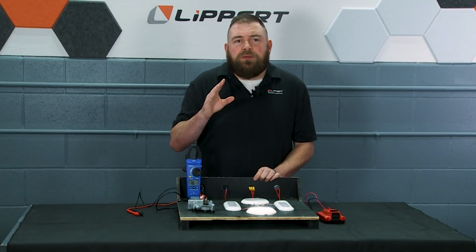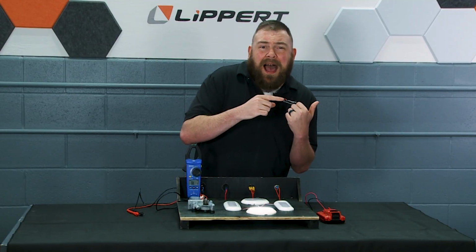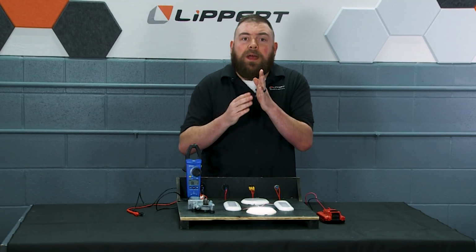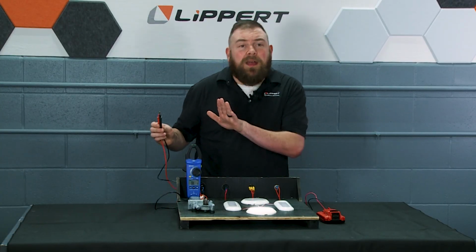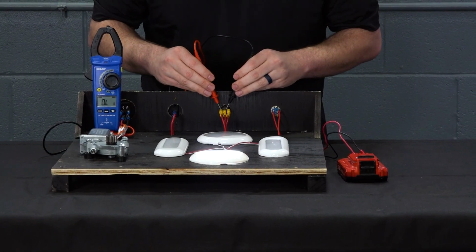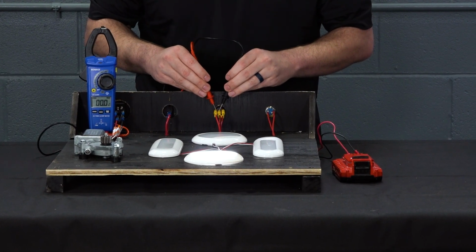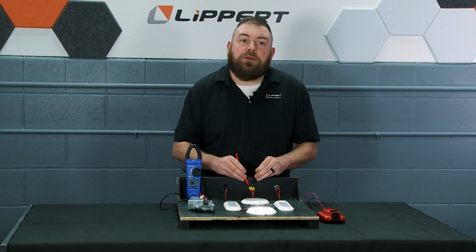Now when I troubleshoot these, let's say I activate the switch to the left, I am going to probe the middle and the right side of the female spades. And what I mean by that is right now it's rocked to the left. I would then take my meter and probe the middle and the outside. And what I'm looking for is that I have that continuity. Now you can see that the light is on.